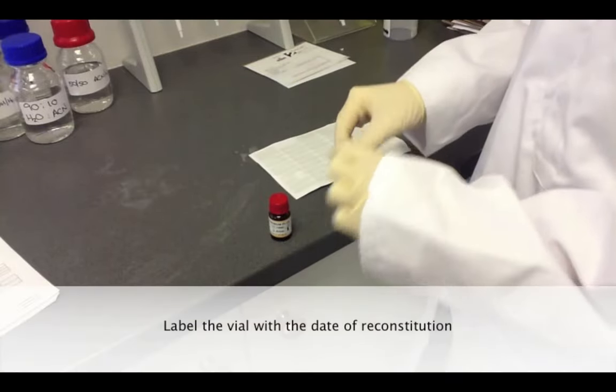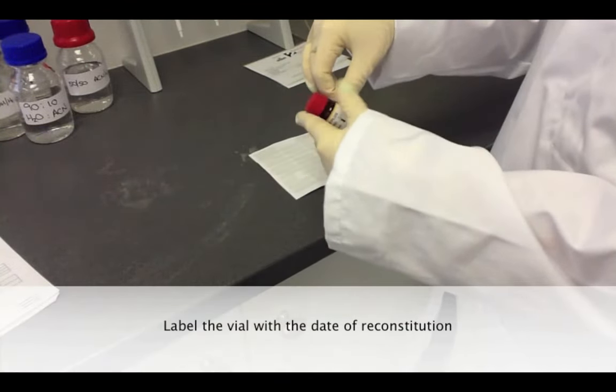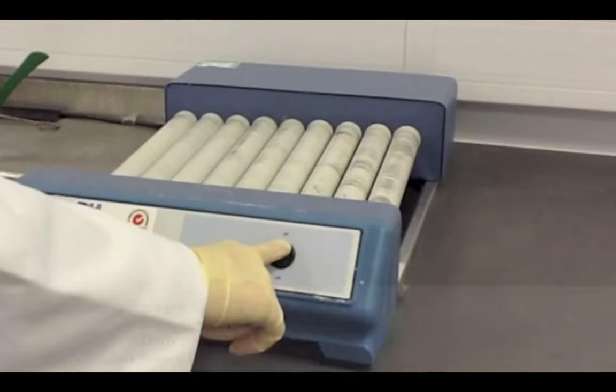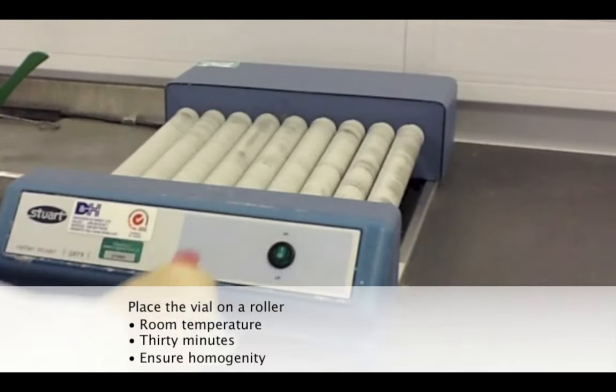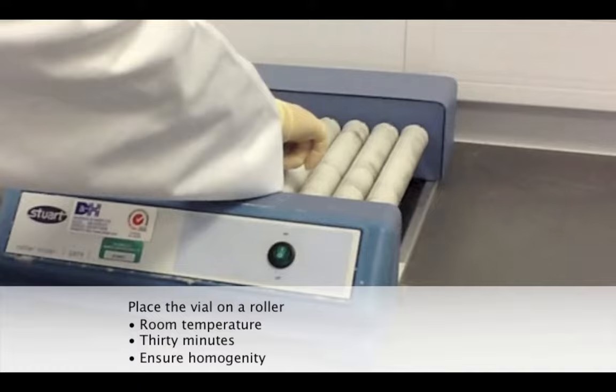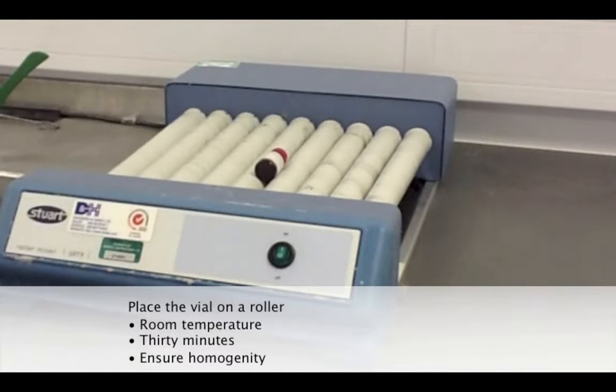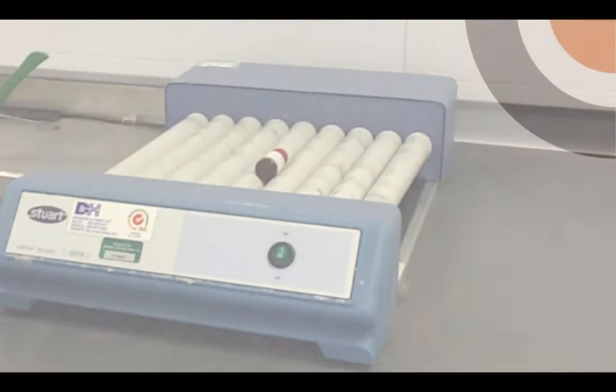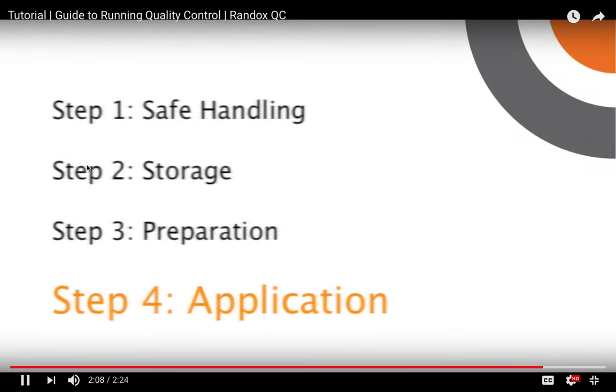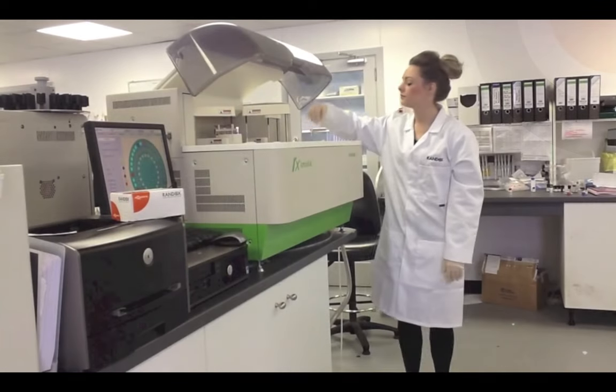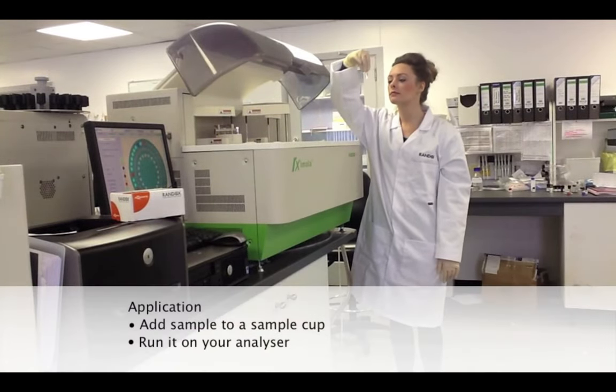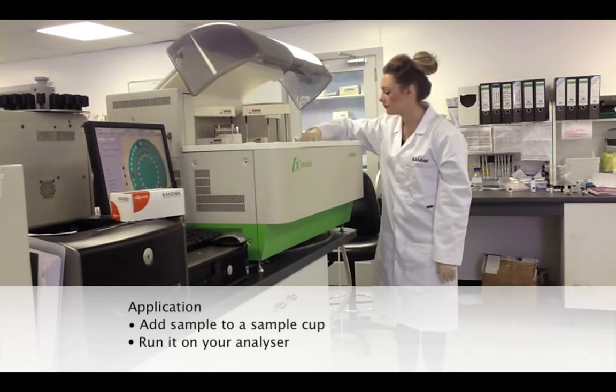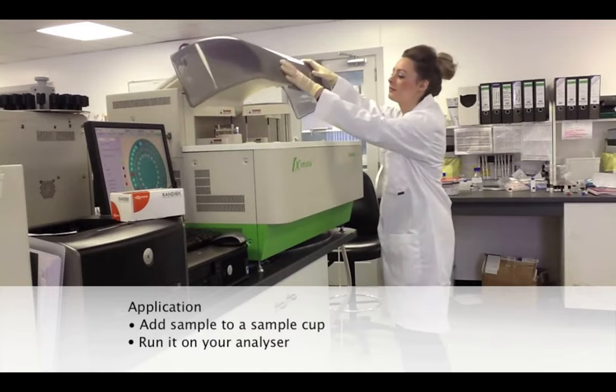Ensure you label the vial with the date of reconstitution. Place the vial on a roller at room temperature for 30 minutes to ensure homogeneity. Finally, add the sample to a sample cup and run it on your analyzer.